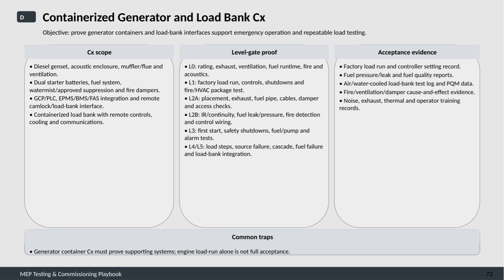We also look at auxiliary systems like dual starter batteries, the fuel system, water mist or approved suppression systems, and fire dampers. Integration points such as a generator control panel or PLC, EPMS, BMS, and FAS interfaces, as well as the remote camlock and load bank interfaces, are also tested. Additionally, the containerized load bank comes with remote controls, cooling systems, and communication links that need thorough validation.